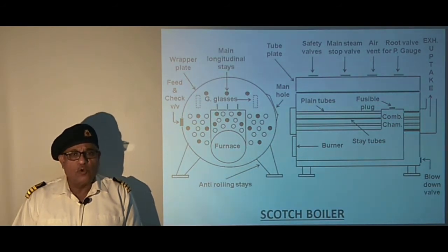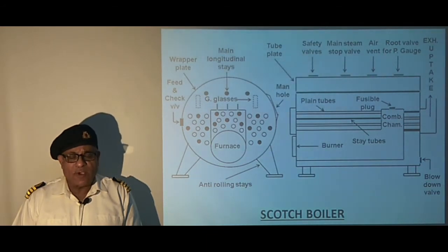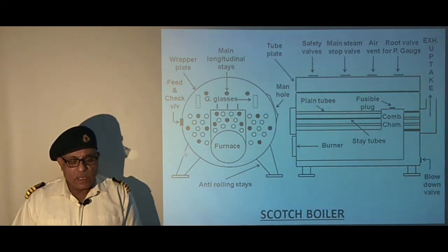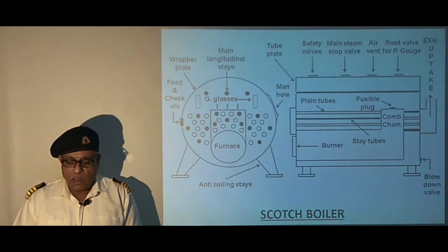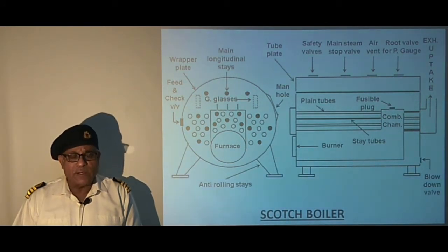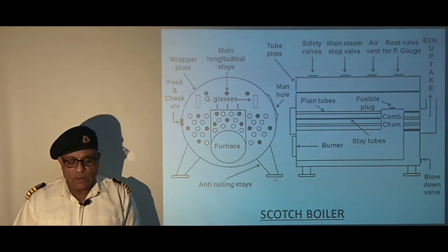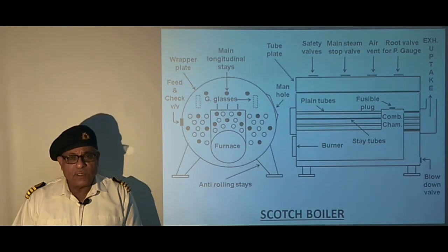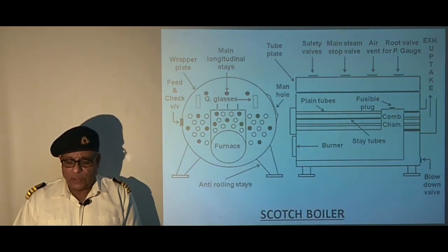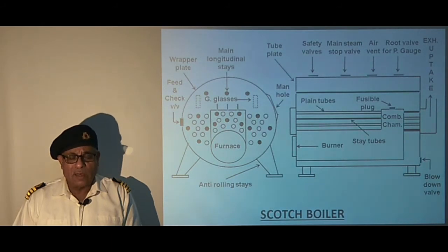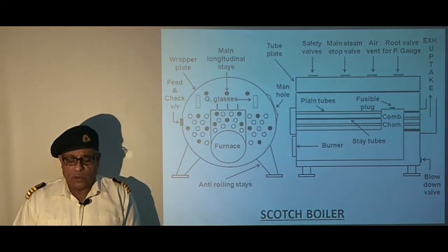The main wrapper plating is usually in two parts joined by double butt welding, which forms the main pressure part — that is the main drum. The boiler is mounted on its foundation with 4 anti-rolling chocks, of which the two front ones are fixed whereas the other two are sliding type to provide free expansion of the boiler, thereby avoiding undue distortion.